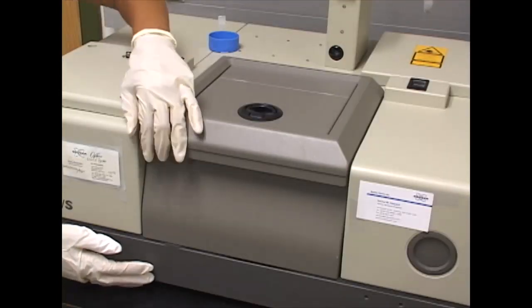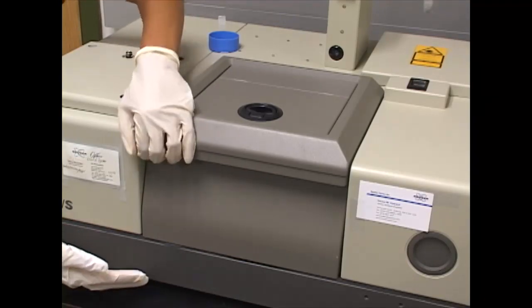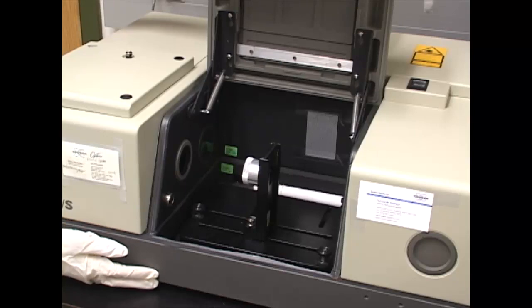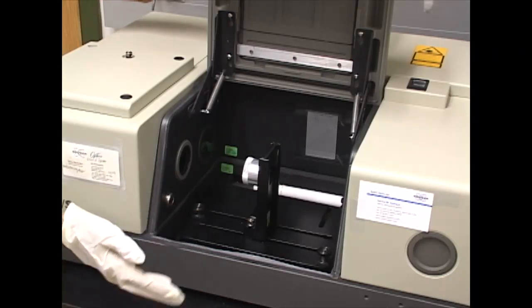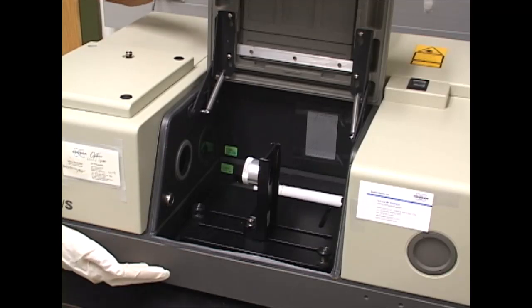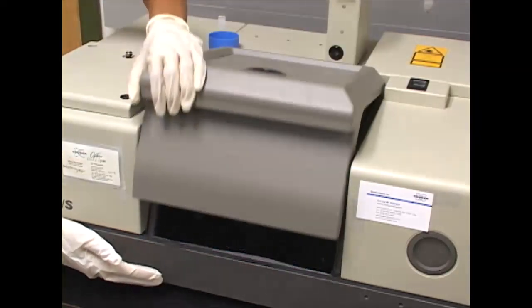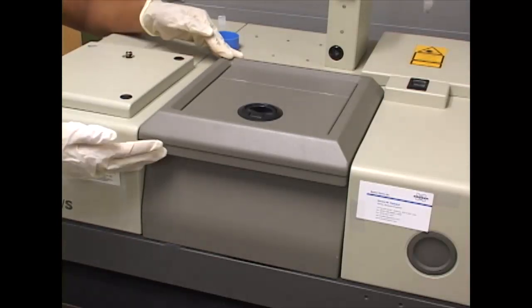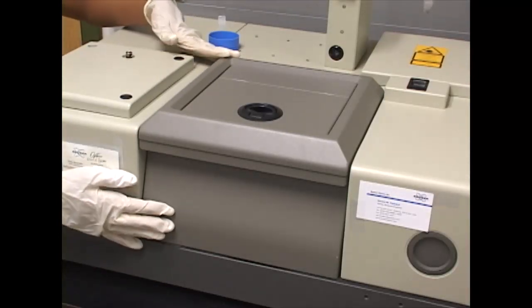A note: with this FTIR, when you are using a purge system, keep in mind that when you open the cavity box, you are letting atmospheric carbon dioxide and water vapor in. So once you close it, you'll have to let it purge for about 15 minutes or so, until you no longer have carbon dioxide and water vapor signals.